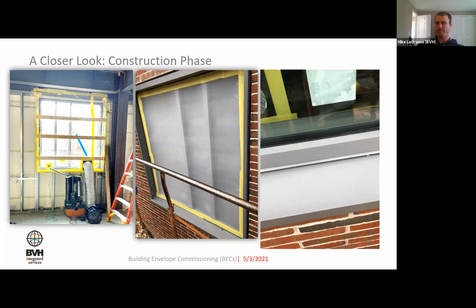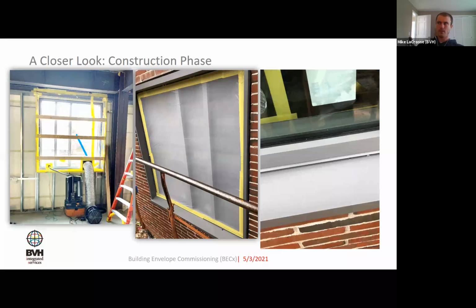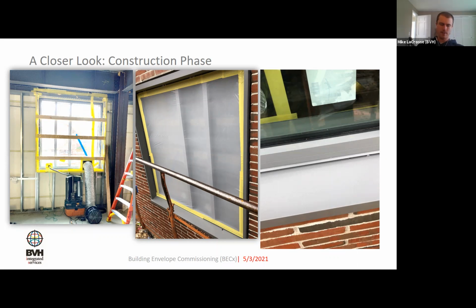So for instance, this unit that we tested, if I remember right, was rated in the laboratory at 10 pounds per square foot, which translates to about 480 pascals. That's much, much higher than the 50 pascals you might use with a blower door test. It exhibited a certain level of air leakage at that pressure. They set a threshold for air leakage, saying we don't want our system to exceed this much, and they go up to the pressure it can withstand before it exceeds that leakage. In this case, it went all the way up to 480 pascals before it crossed that threshold.